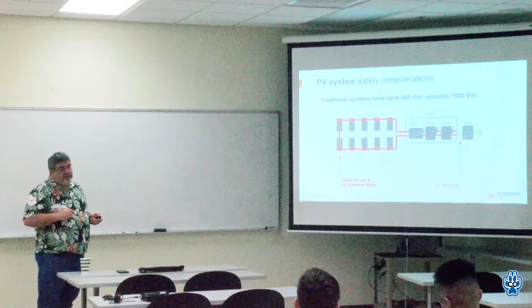But it comes with its own set of problems. If we go back to the string inverter, I have one inverter located on the house. With the microinverters, you've got lots of them. That's kind of good and bad, actually, because if one of these goes bad, the rest are still running. But if I lose my string inverter, I've lost it all - if that fails, everything's down, you get nothing. At least with the microinverter system, there's some resiliency through redundancy that really helps out with the overall output. So when you think about it for a house, maybe it doesn't make a whole lot of difference.